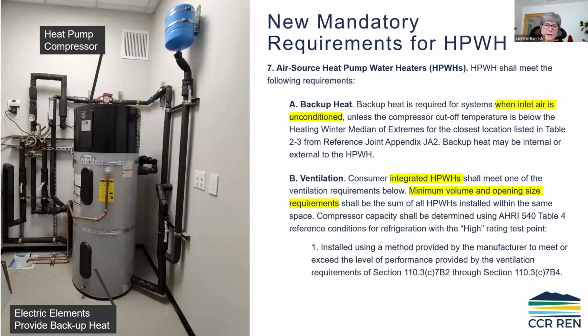What we've been telling architects as a rule of thumb, based on research done for heat pump water heaters, is to start with 450 cubic feet of room volume if they have the space. You could combine it with a utility room or laundry room—something like 7.5 feet by 8 feet by 8 feet tall.